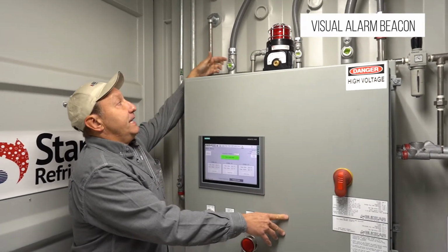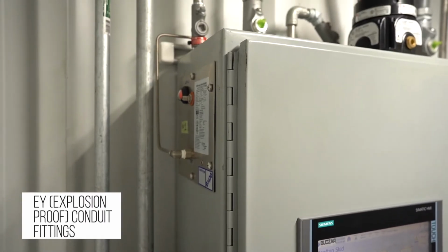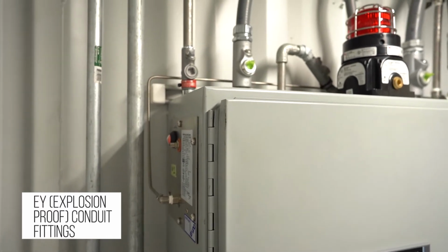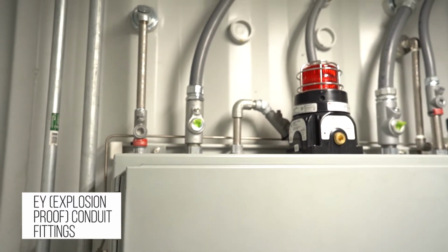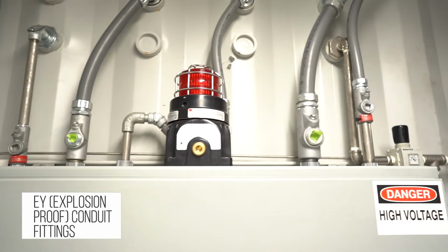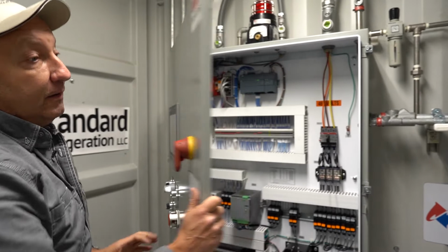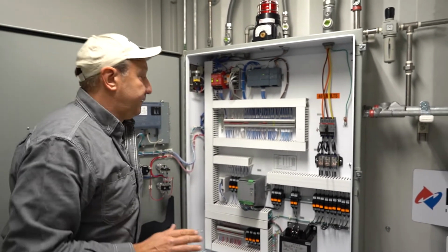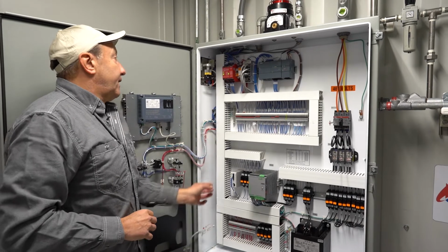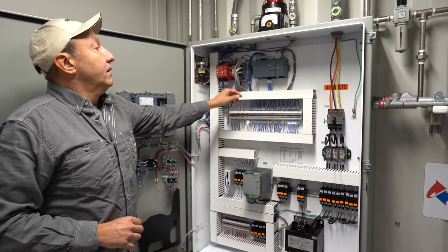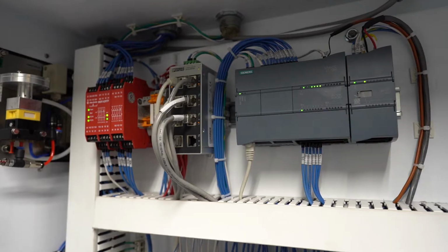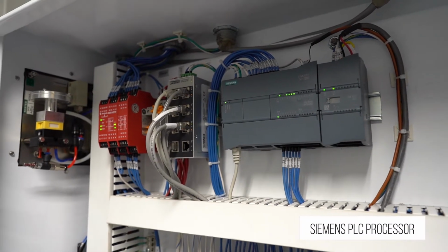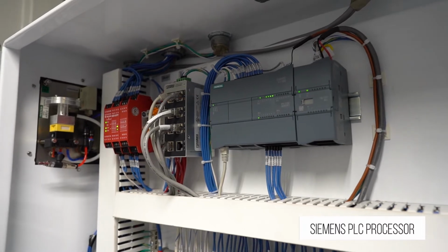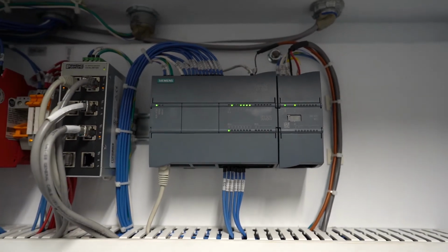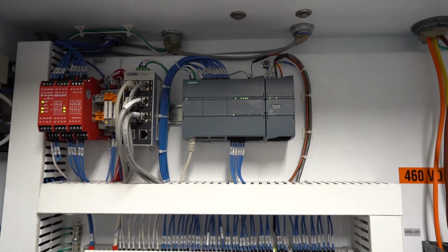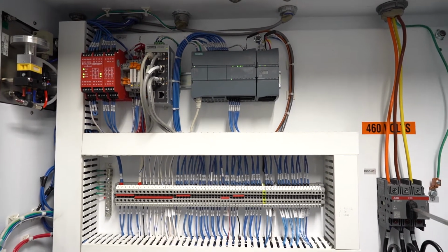Everything is utilizing EY conduit fittings. Because of the purge panel system and the volatility of the propane, every enclosure has a purge system at 1 inch of water column. Inside here, this cabinet is energized, so we're going to be very safe, of course. We have our e-stop safety switch, our Ethernet switch, and this is the brain of the system. This is our Siemens PLC processor, and it has a set of I/O racks for inputs and outputs, RTDs, things of this nature. Most of the cabinet is 24 volt DC, the blue and white and blue wire. We have a little bit of 120 in here.